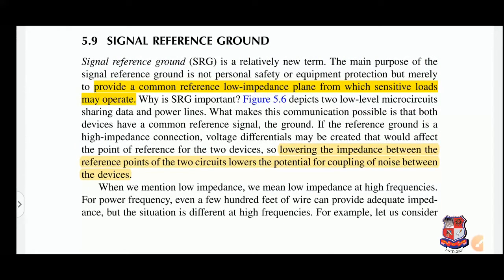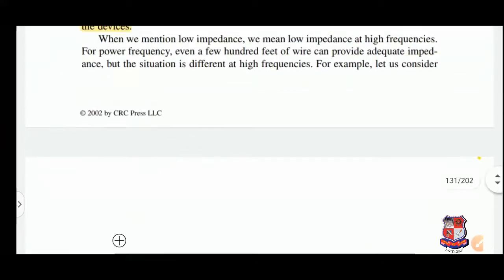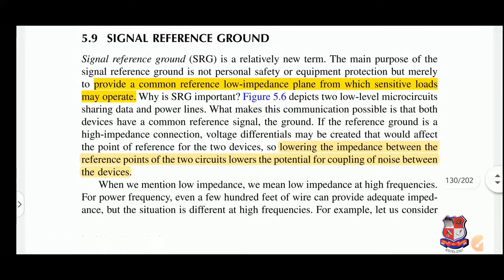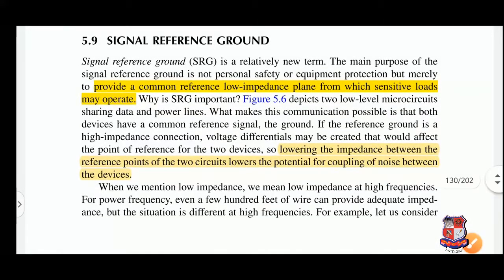If the reference ground is a high-impedance connection, a voltage difference may be created that would affect the reference point for the two devices. With high impedance, a small amount of current will create a voltage drop, causing a problem in communication. Lowering the impedance between the reference points of the two circuits lowers the potential for coupling of noise between devices. Noise refers to any unwanted signal that comes along with our data.